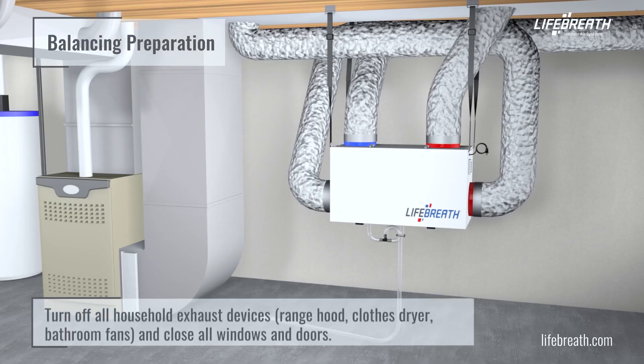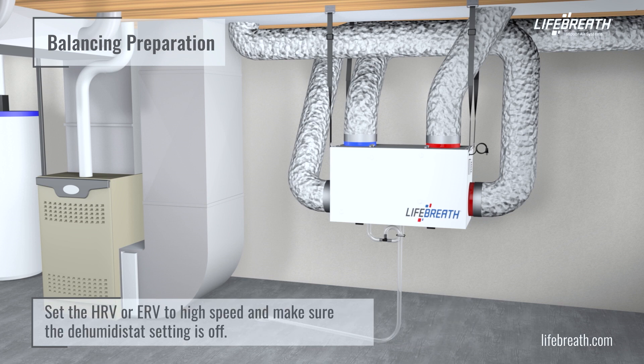Turn off all household exhaust devices — range hood, clothes dryer, bathroom fans — and close all windows and doors. Set the HRV or ERV to high speed and make sure that the dehumidistat setting is off.